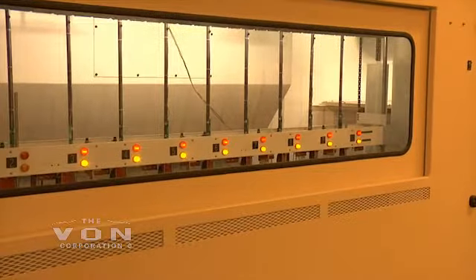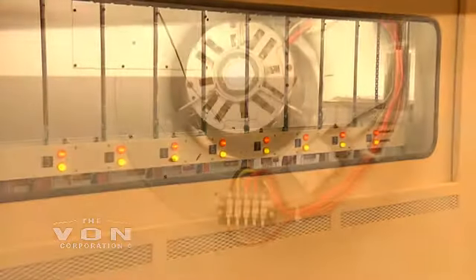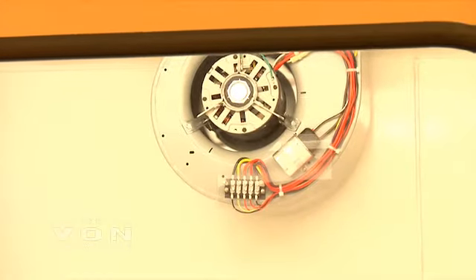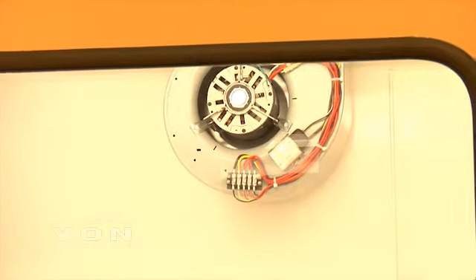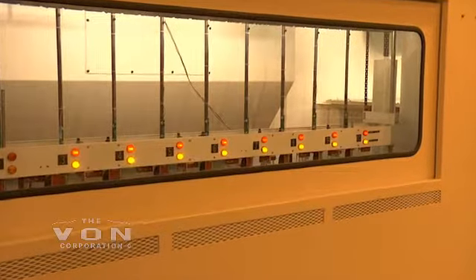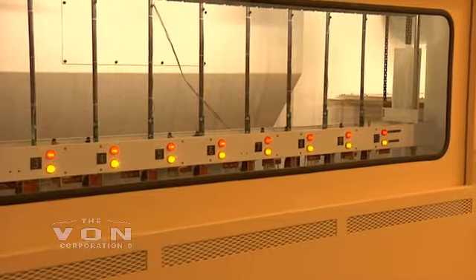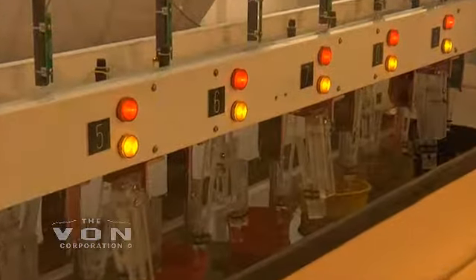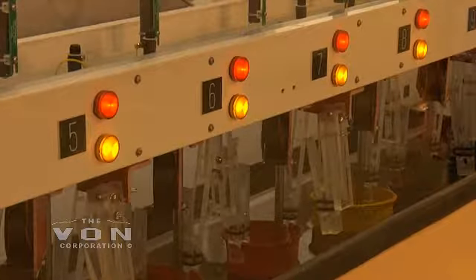Right now we have it preset for one minute. The exhaust fans have come on automatically because we're testing AC. Our voltage has automatically risen to 5,000 volts, just as ASTM has mandated that it rise so many volts per second. The test has now started — we're 22 seconds into the test.